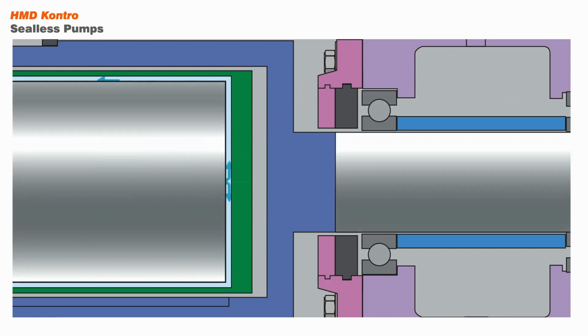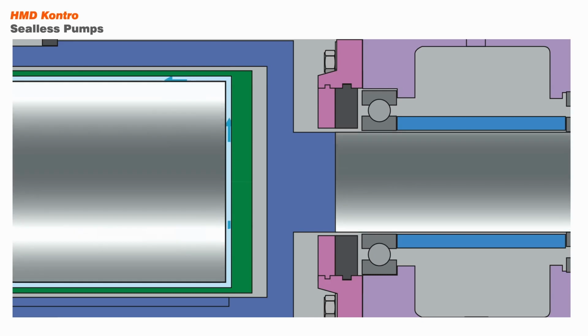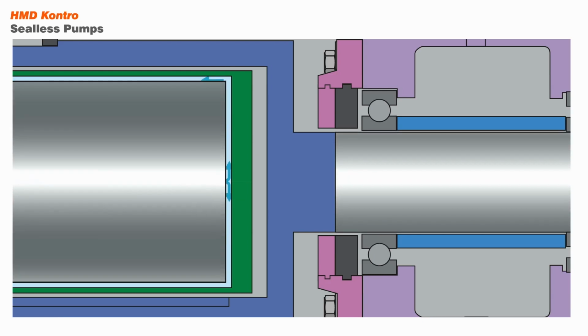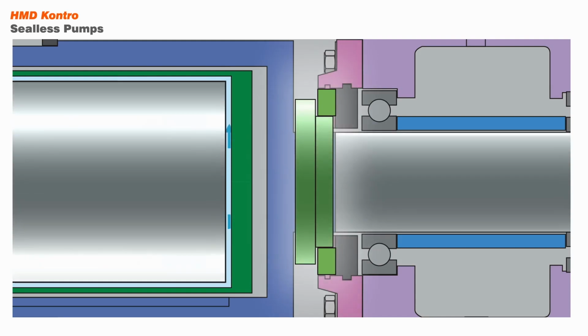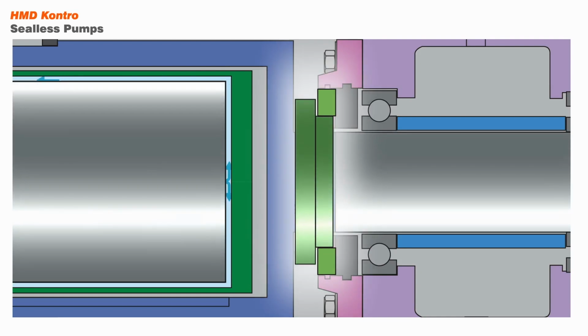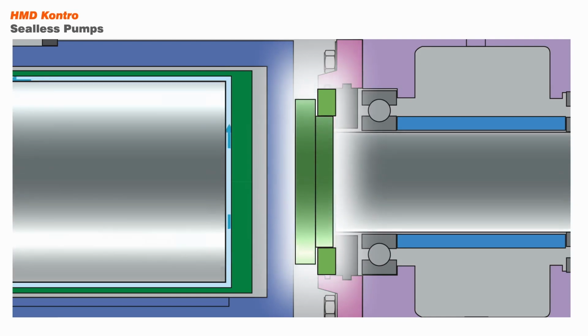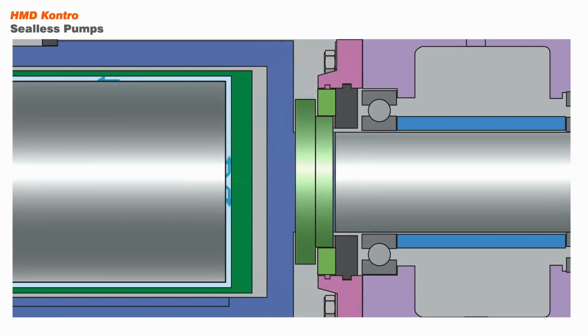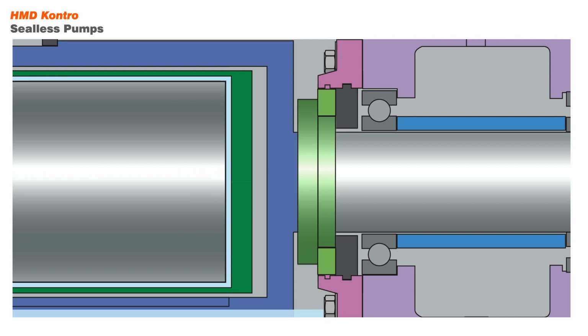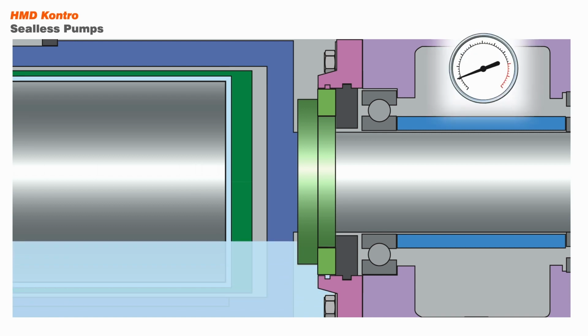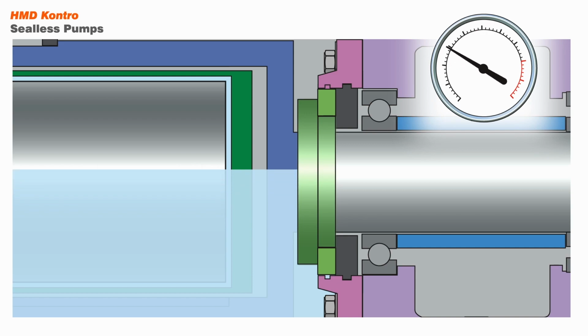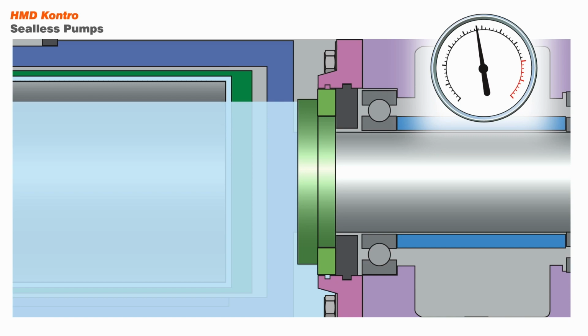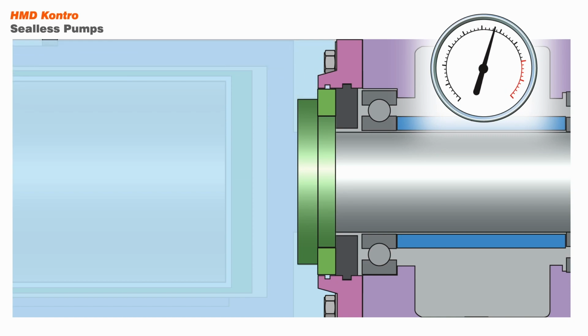With magnetic drive pumps, a gap exists between the magnetic coupling driveshaft and the coupling housing. The gap is sealed by a dry-running mechanical seal. Under normal operating conditions, the two faces of the seal are non-contacting. In the unlikely event of a primary pressure breach, the instrumentation immediately stops the pump, enabling the mechanical seal faces to close. As the liquid builds within the outer shell, the area surrounding it is filled with the liquid, but the secondary containment seal prevents any leakage. Pressure can build within the secondary pressure boundary, and the mechanical seal will contain the liquid, preventing any leakage to the outside atmosphere.